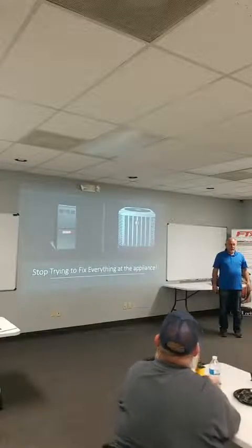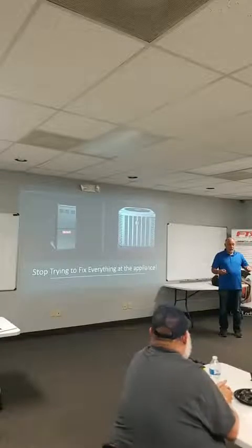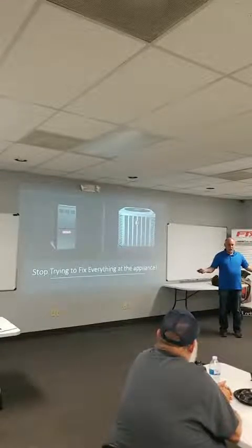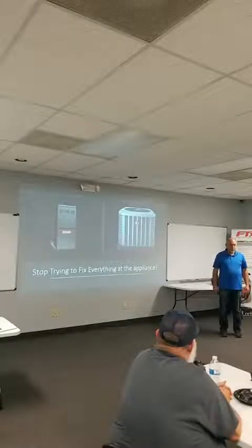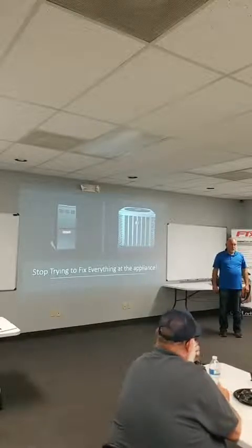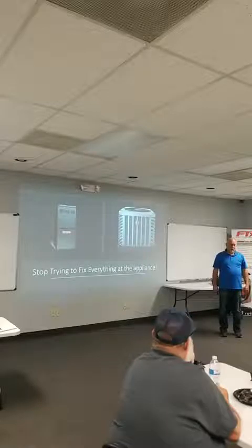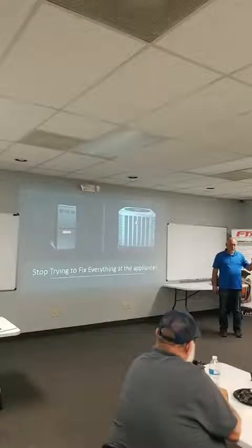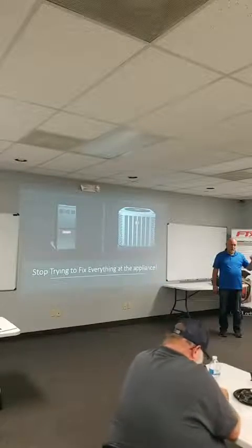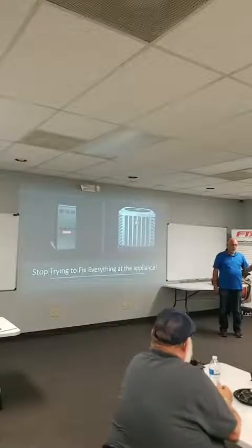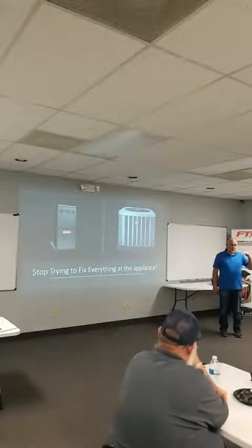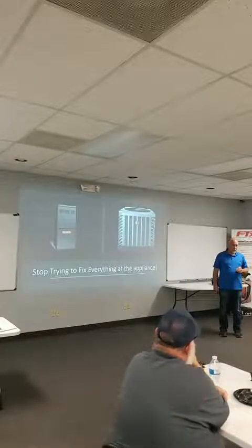So finally I got Stark State to let me go in there, and what was happening was, I noticed that when I walked down the hallways, it was like a wind tunnel in the hallways. The whole building pressure was just screwed up everywhere you went. And the hot deck, cold deck boxes, the ducts were constantly blowing off the boxes. They just blow right off. Well, the thing was running 6 inches of static pressure. Wow. It was supposed to run, I think, 2 inches of static pressure. So finally got them to invest in a variable frequency drive. We put a drive on, we dropped it down from 60 hertz down to 30 hertz, maybe 35 hertz. Dropped the static pressure down from 6 inches down to 2 inches of static pressure.